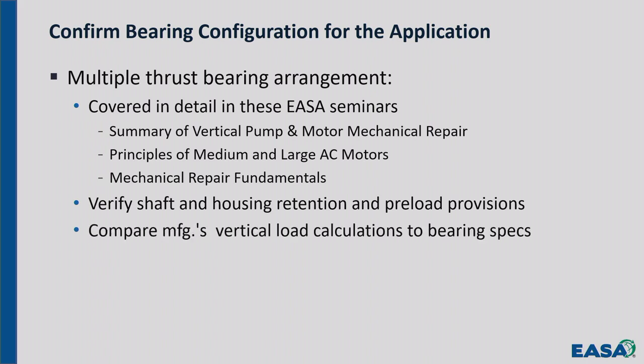The pump manufacturer, when a pump was designed, provided some sort of axial load specification that the bearings in the initial motor were designed to hold. So if you're switching motors back and forth, or your customer is, somebody needs to do this calculation of the load for those particular bearings. And if you check with your bearing supplier or just look it up in the catalog, there is a dynamic load rating for all vertical bearings. And there are some calculations that need to be done to come up with it. They're not simplistic. They're not particularly complicated, but don't think you're just going to read a number off the table and not have to do any multiplying or dividing. There are some factors that need to be applied to come up with the load rating for that particular bearing. And then you have to know what the load is from the pump.